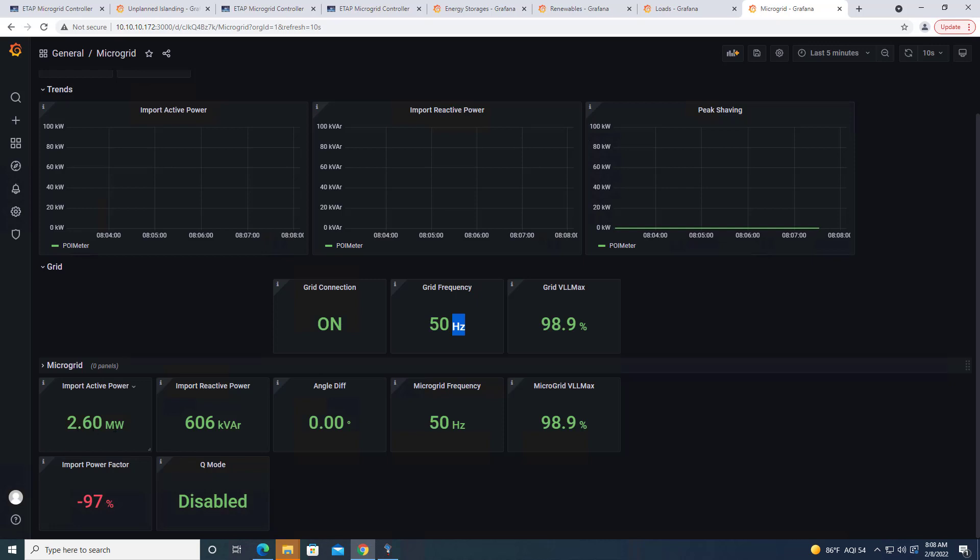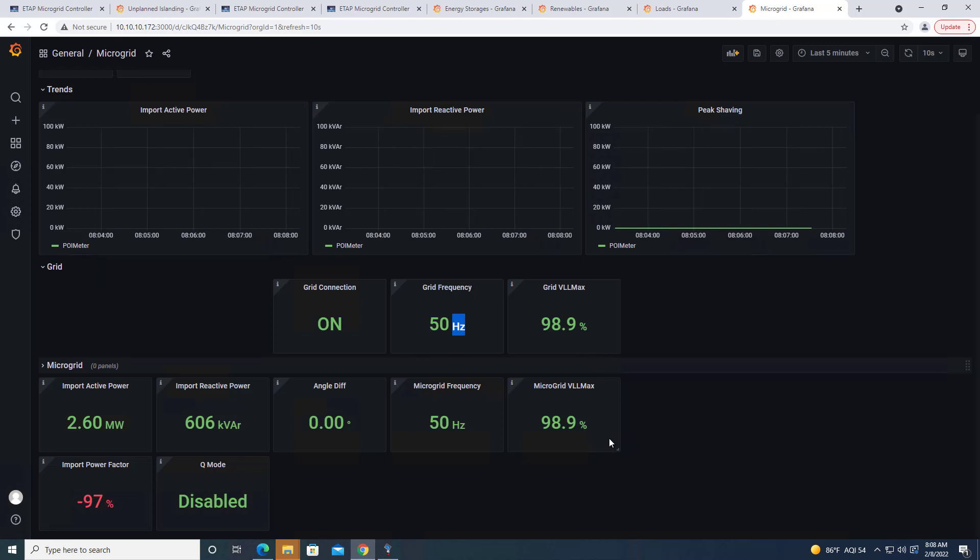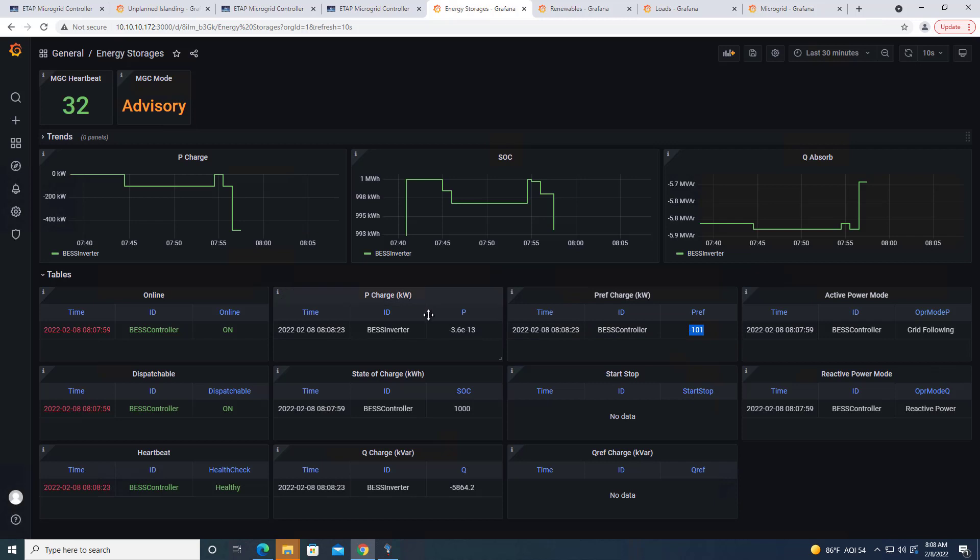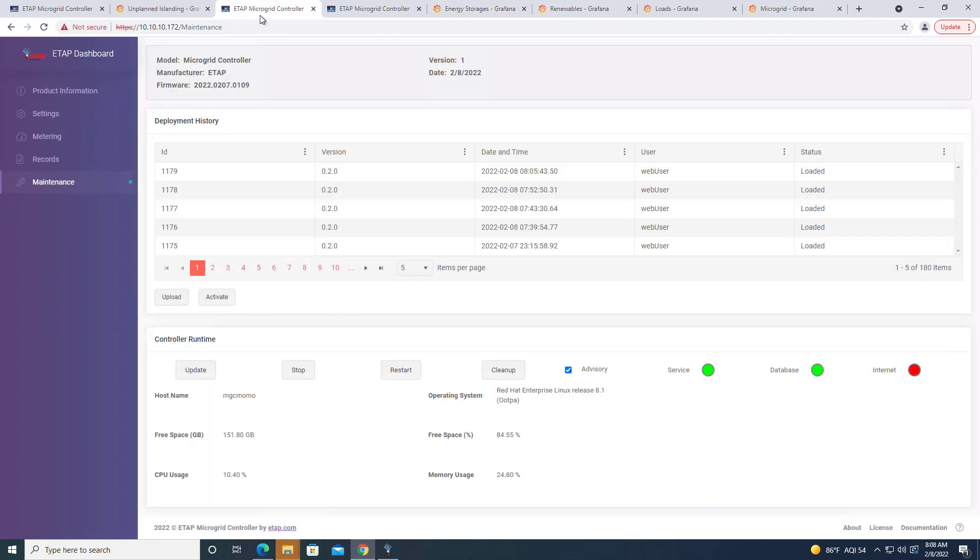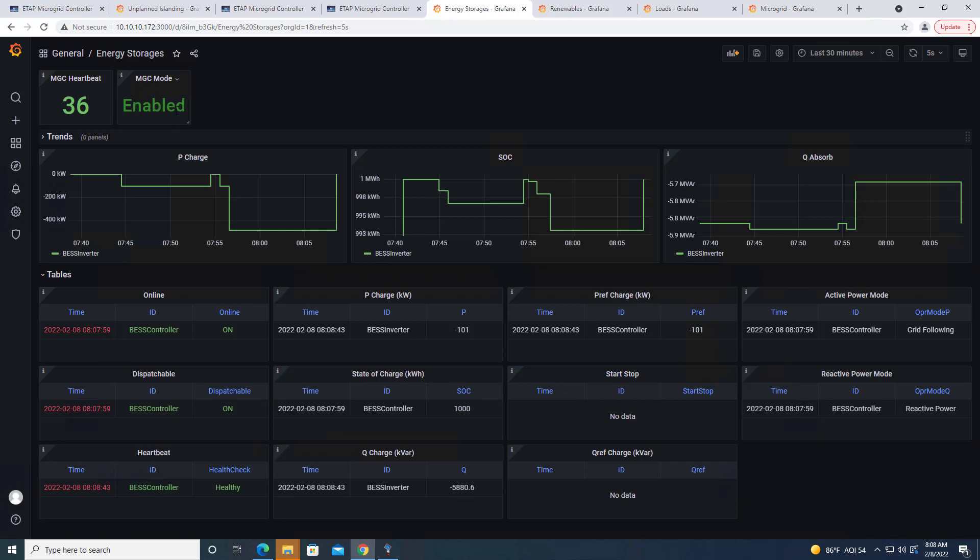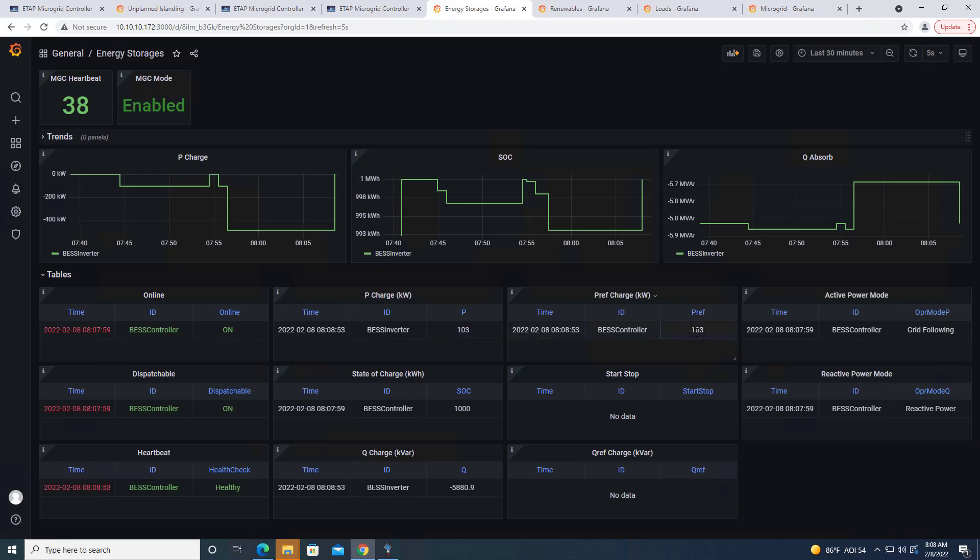We have about 2.60 megawatt input from the grid. Frequency is 50 hertz. I have about 98.9% voltage at both sides of the grid and microgrid. We can look at our energy storage at this point. We have a command, but microgrid is in advisory mode, meaning it doesn't send any command. The microgrid doesn't charge. If I go here and say I want to go out of the advisory mode and come back to energy storage, let me increase the resolution here. In about a second or so, we're going to be switching to the enabled mode. Microgrid controller sends a command of 103, and we are discharging 103 in the system too.